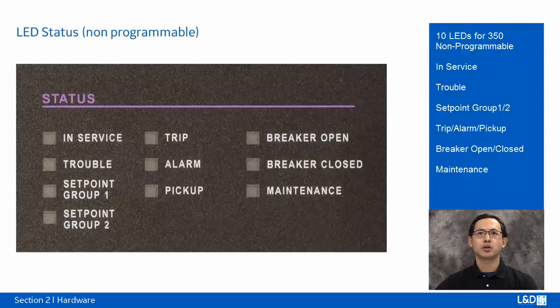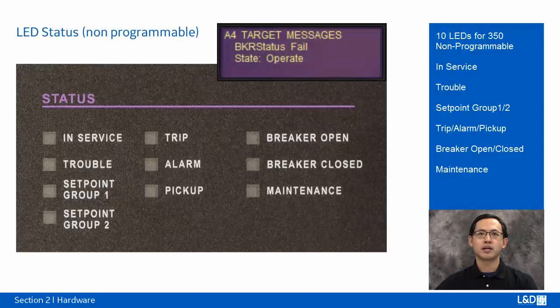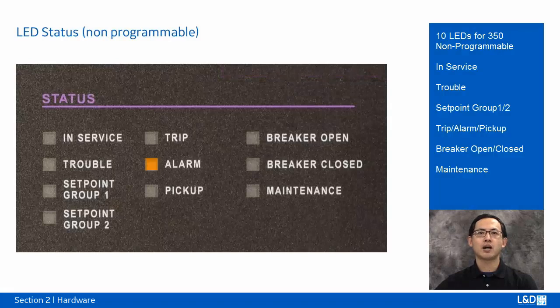Both breaker open and closed LED indicators will be off, and the relay will display a breaker status fail alarm message, and the alarm LED will also flash in orange color.